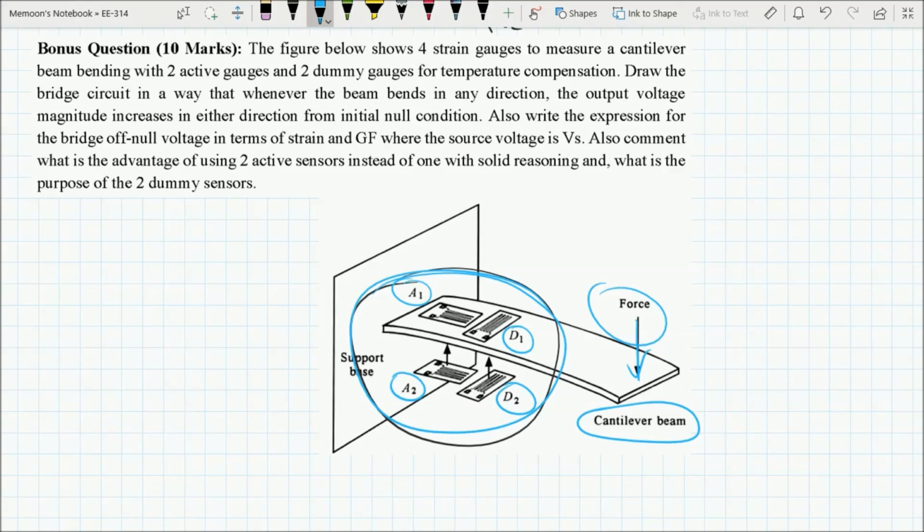For example, if there was a strain gauge used to measure the strain, and the change in strain was producing a change in resistance, the strain gauge was operated in a bridge and current was passing through it, and due to that some power was being dissipated across that strain gauge. That power dissipation will result in a rise in temperature of the strain gauge, and the resistance of the strain gauge will also change because of the change in temperature in addition to the change in strain.